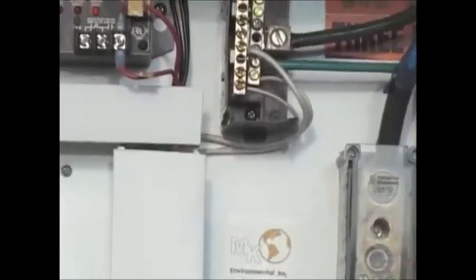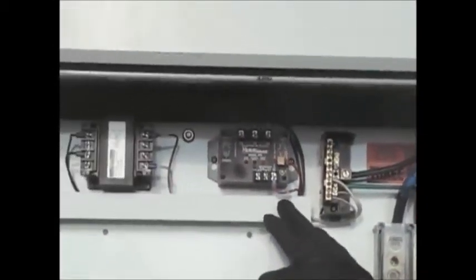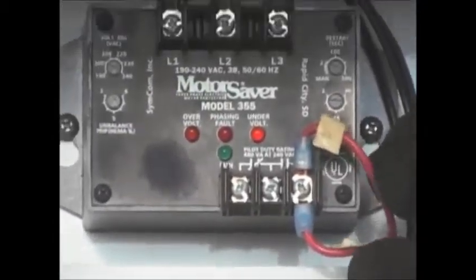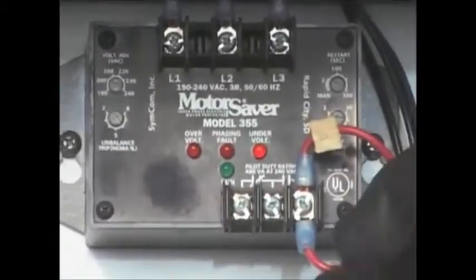There is a motor saver device up here. This device is basically monitoring the main power coming in. If the main power fluctuates down, if you get a high voltage or a low voltage, basically it would trip the system out. Currently, this item does not work, and we have circumvented or bypassed it so that we can demonstrate today.